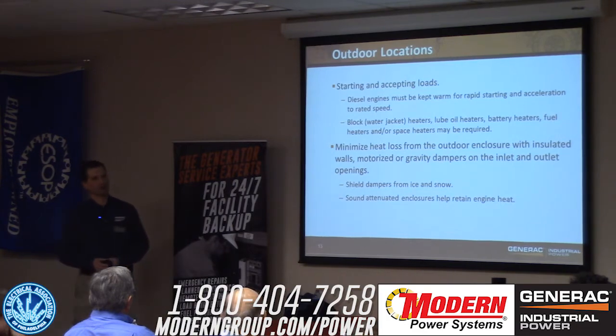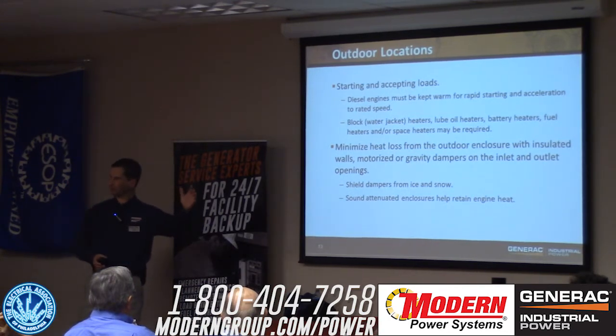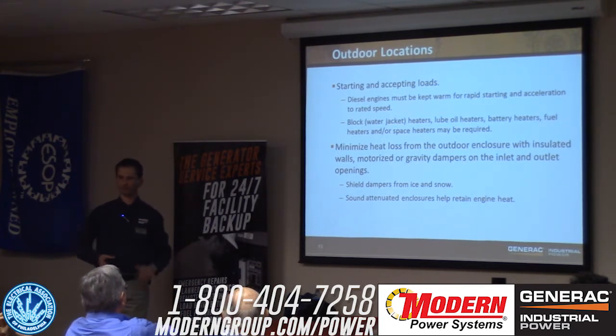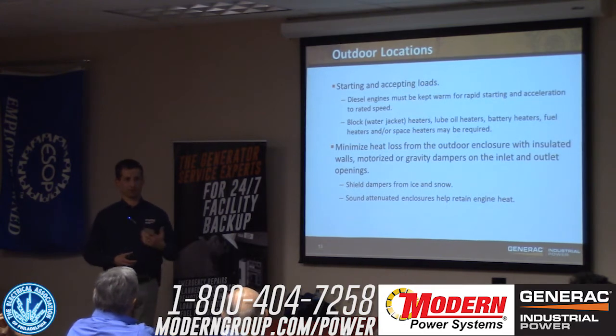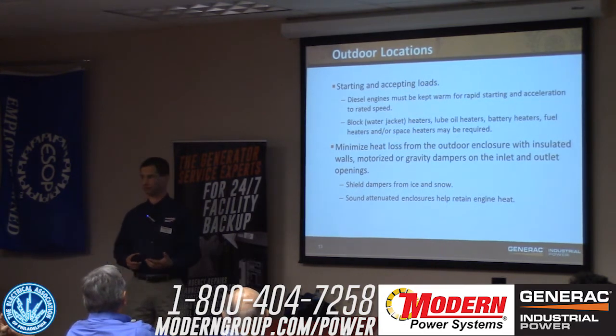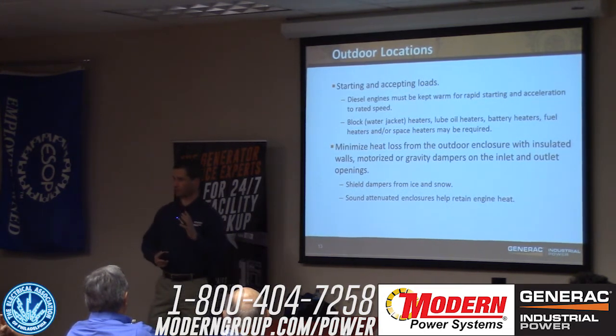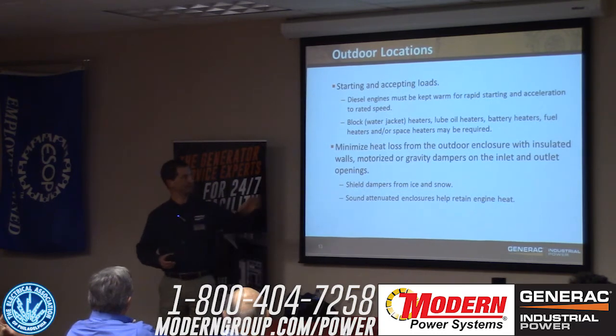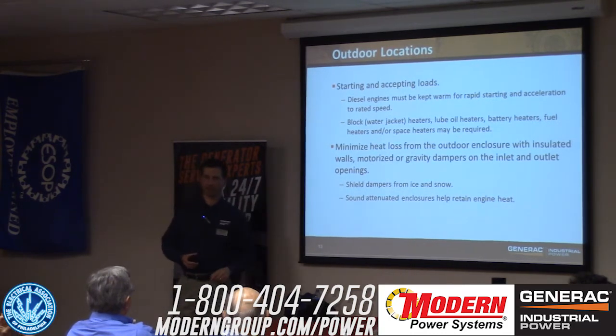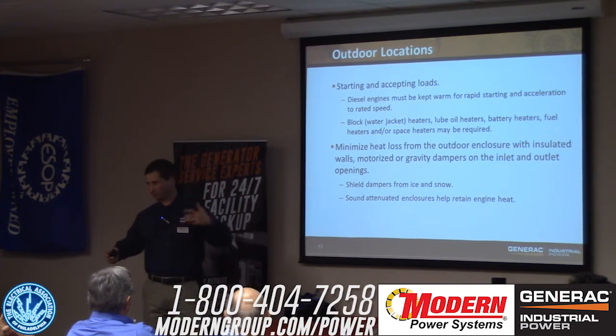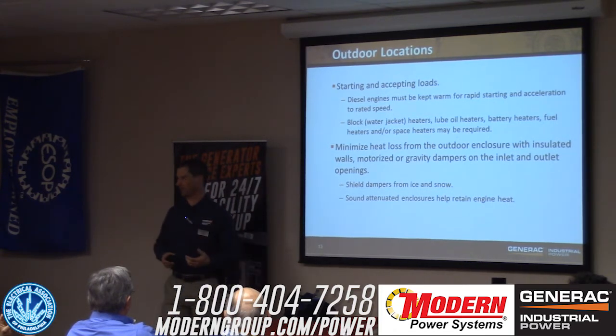In colder climates, not so much here in the greater Philadelphia area, but up in upstate New York or New England, you'll start seeing options like motorized dampers to help keep heat inside the enclosure. You'll also start seeing, in addition to a block heater on the engine, a space heater inside the enclosure, maybe 2,000 to 5 kW for larger enclosures.